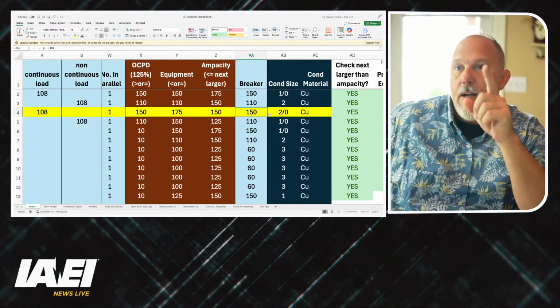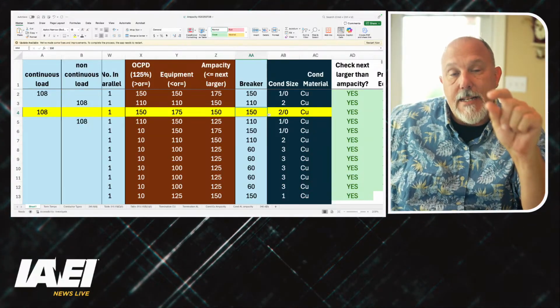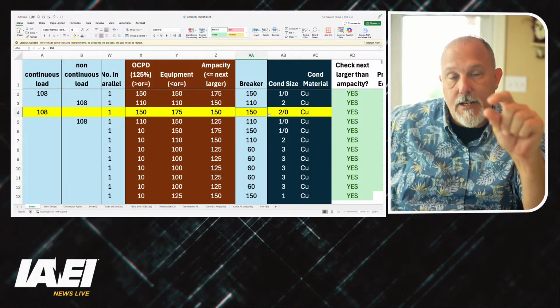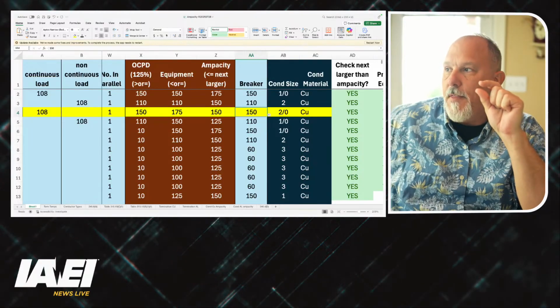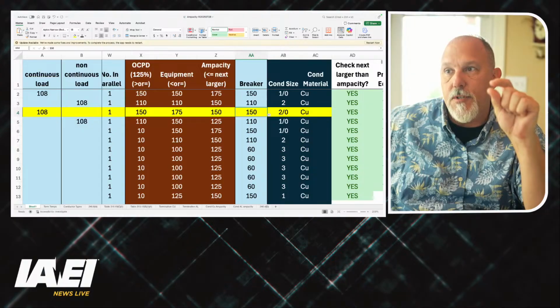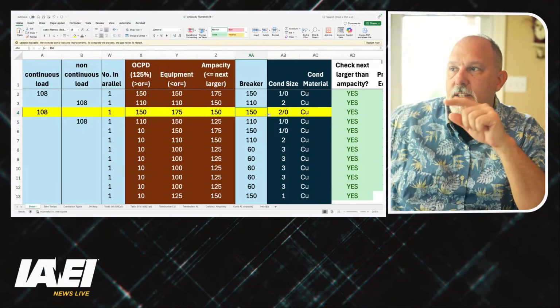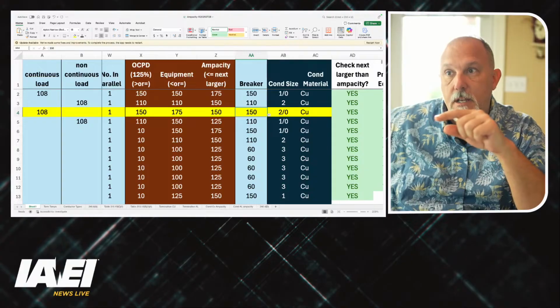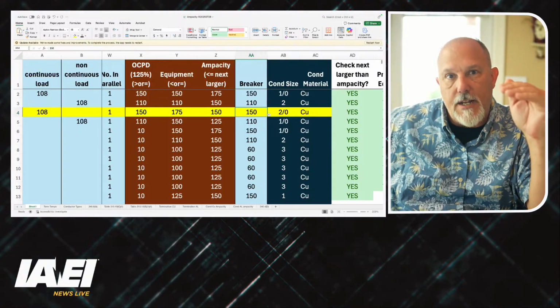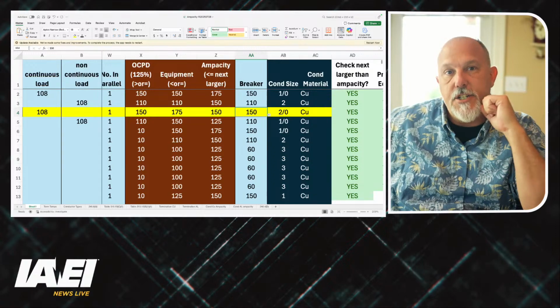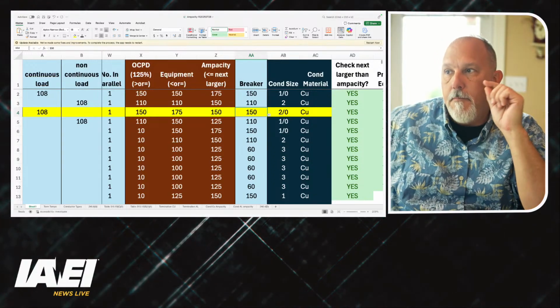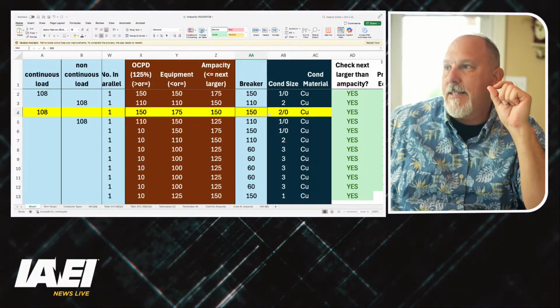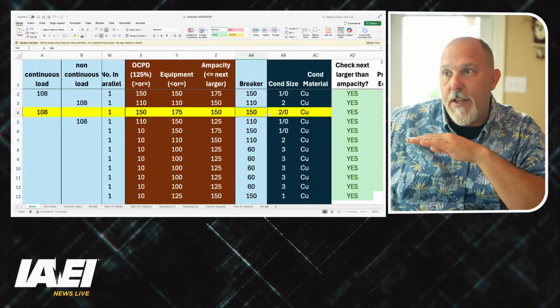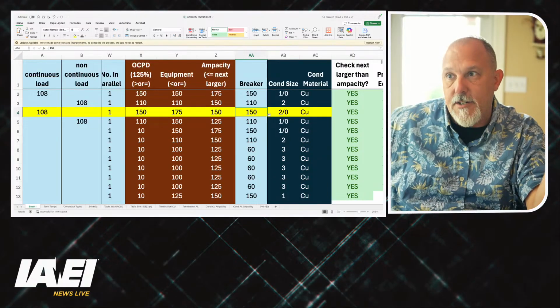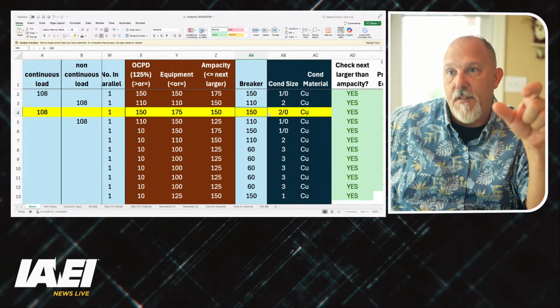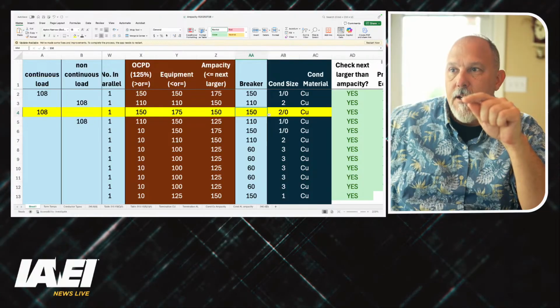So I was not protecting the conductor at its ampacity when I was using a 1/0. So in this case, for 108 amps of continuous current, because of the ampacity adjustments, I had to increase the conductor size based on conditions of use.